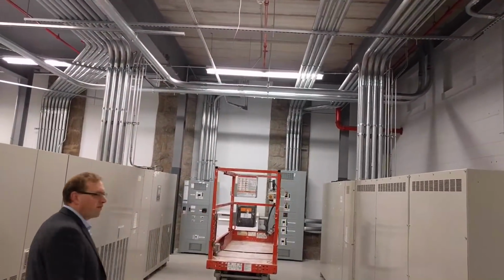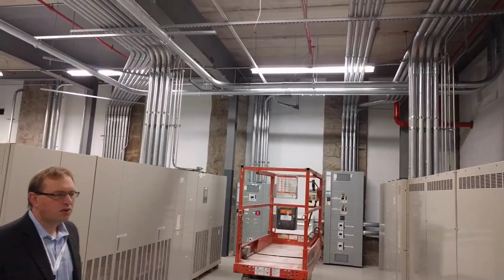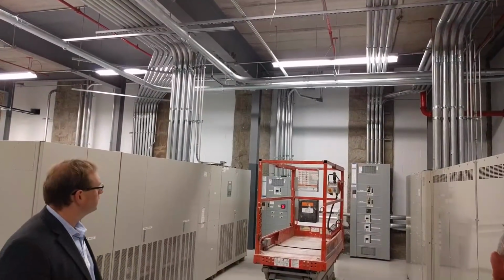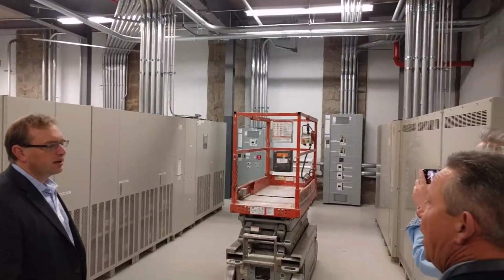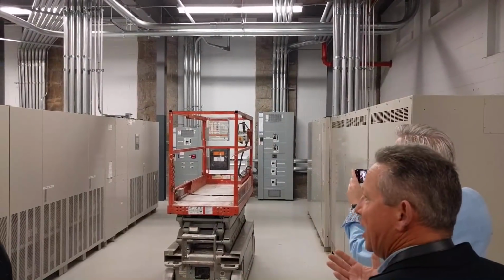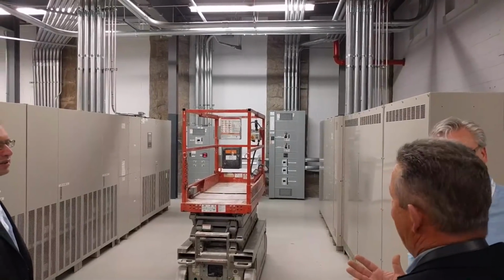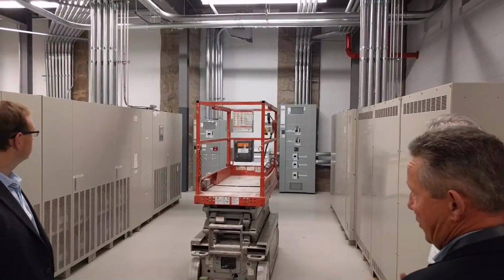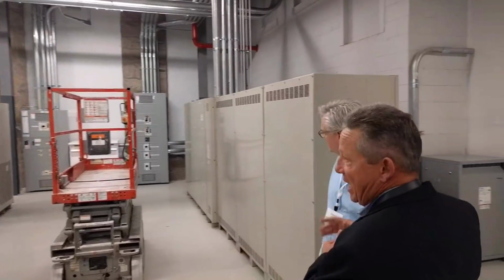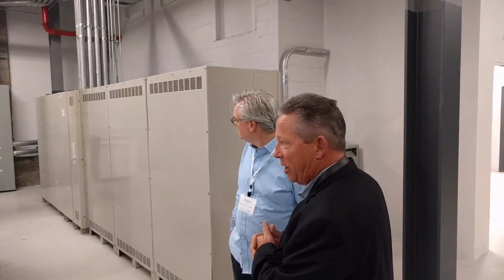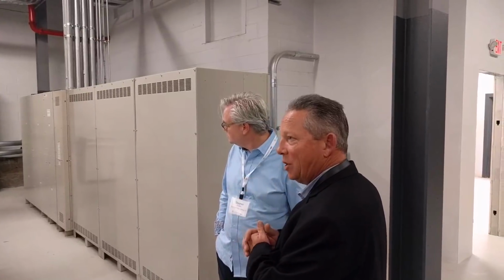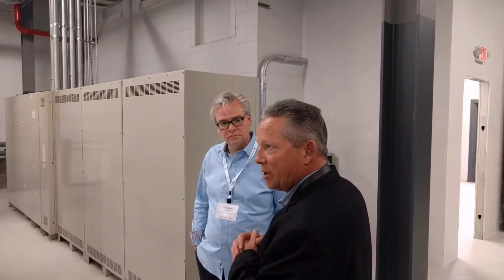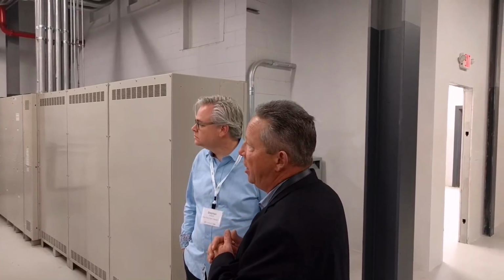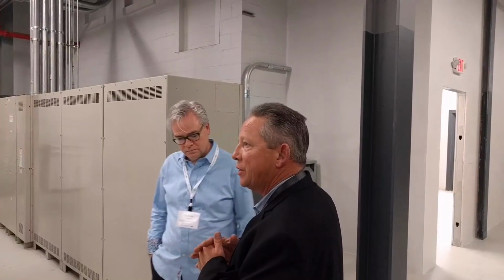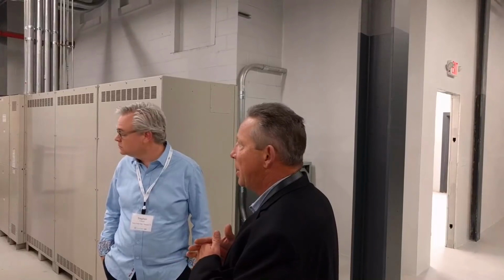So we can take the UPS inverters and shut them offline without interrupting power to the transformer. Then we can put the utility in parallel with that. Then we can remove the UPS from that parallel circuit without interrupting the power to that transformer, the customer circuit. We can take out the UPS, do whatever maintenance we want. We can remove it from the building and roll a new one in, put it back in line, reverse the order, the sequence of operations to bring it back online without interrupting power to that transformer, to that customer circuit. So this stuff can be maintained without shutting anything down.